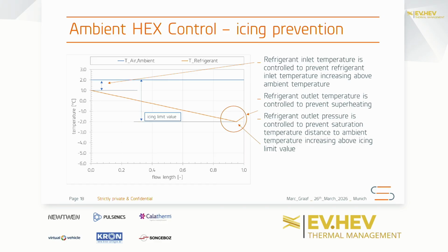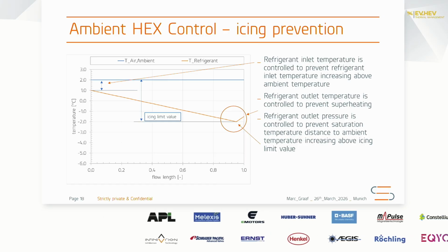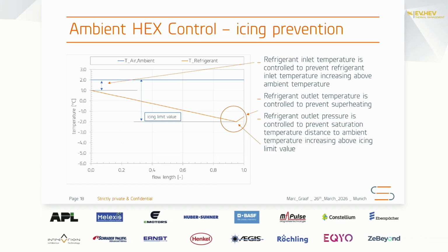So you can allow a much higher airflow and much higher refrigerant flow through the heat exchanger with CO2, and allow a much higher pressure drop. Or you have a lower temperature on the inlet and a higher delta T over the complete surface of the heat exchanger, and you can pick up more heat from the ambient air without icing under the same conditions. So therefore, a CO2 system has a big advantage when you use it as an air heat pump compared to a YF system.